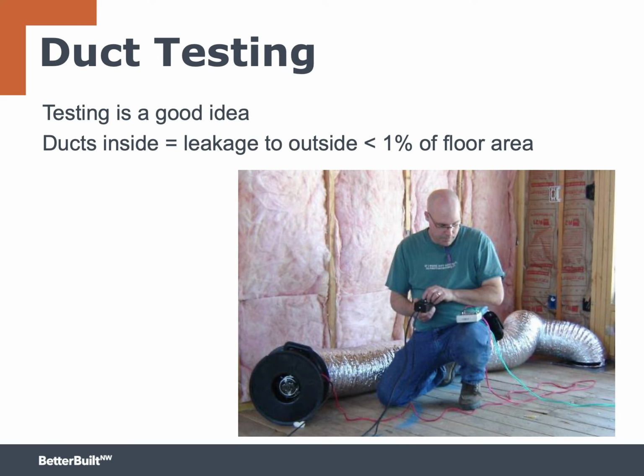When you do a duct test, you'll want to do a test that's called the leakage to outside test. It's a little more complicated than a total leakage test because it requires a blower door and a duct blaster. You're shooting for leakage of 1% of floor area. The standard for most programs is 6% of floor area. So you can see that you're really reducing the amount of leakage from the ducts dramatically. And the duct test will tell you whether you've achieved that 1% leakage target. It's not a standard of any kind, it's just a guideline for what you should probably expect in terms of leakage in an energy-efficient home with ducts inside.